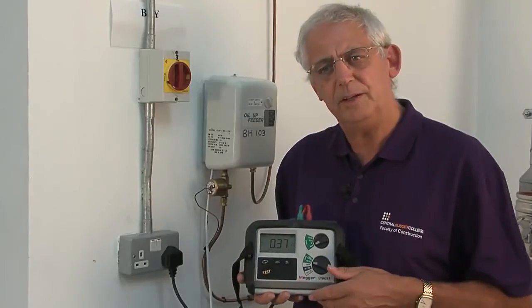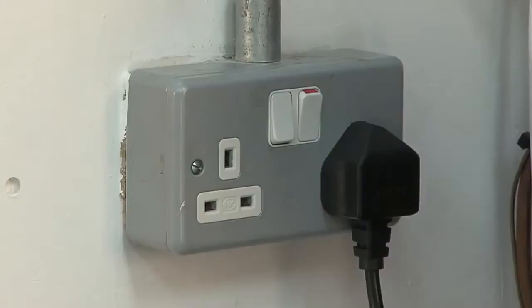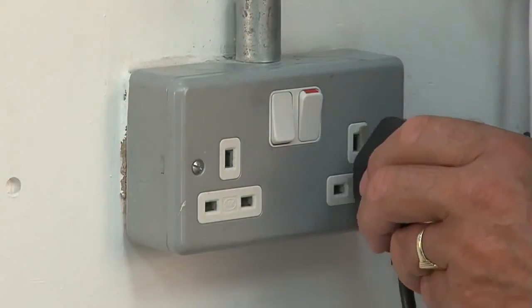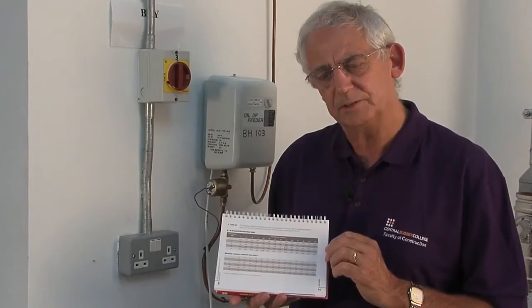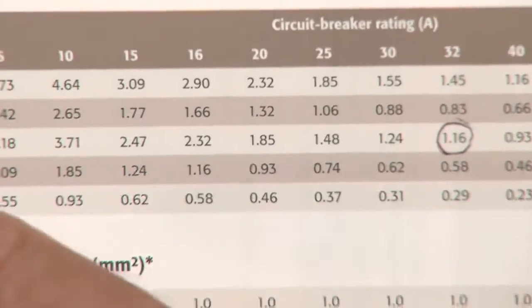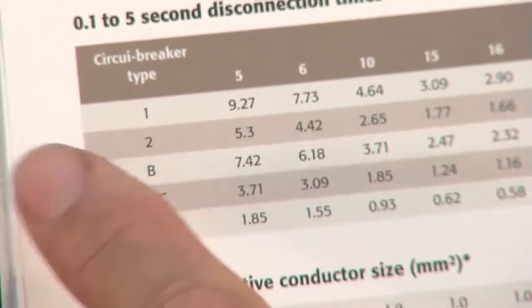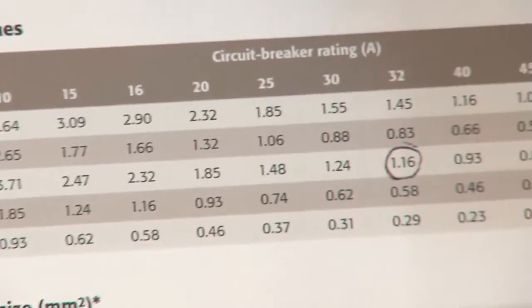I can compare that directly with the tables in the on-site guide. I know I've got a Type B 32-amp protective device. If I use the chart, I can go down the left-hand column to Type B, along the top to 32.